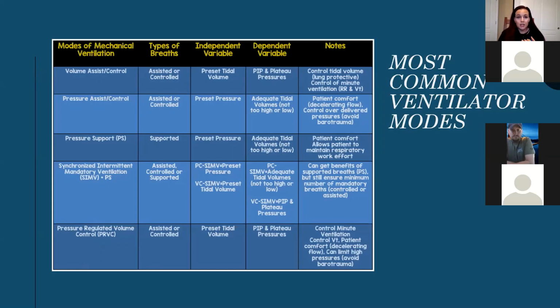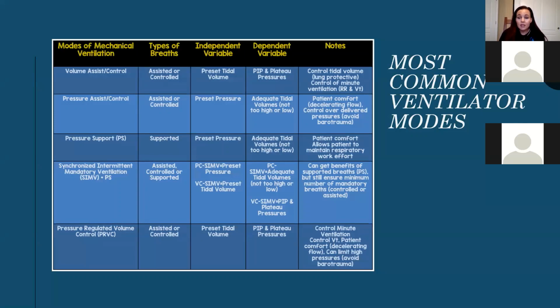So you can see with this chart on here that this is going to show you what you control, what you get to mess with, how much the patient gets to contribute, things like that. So when we break it down, when we're going to do a straight volume control mode, strict volume control modes that don't give you the luxury of SIMV or pressure support or any of those types of things really lock out your patient. So when you set a tidal volume of 400 on there and a rate of 12, your patient will breathe 12 times with a tidal volume of 400, and then your patient, when they decide to take their own breath, will be given 400 no matter what.